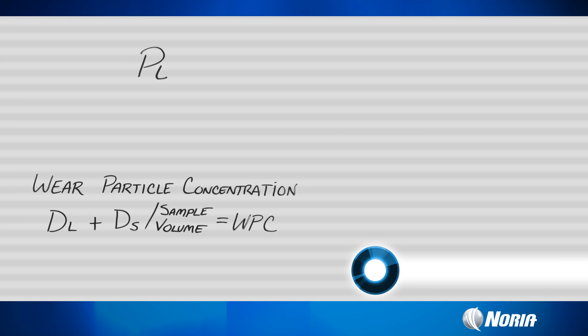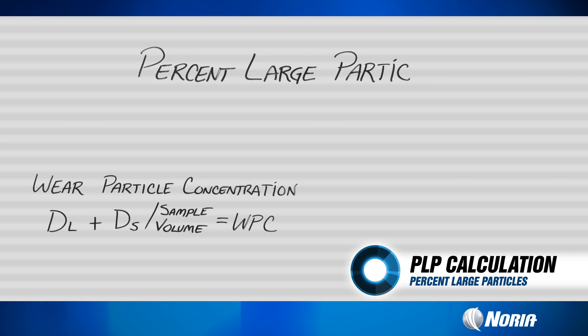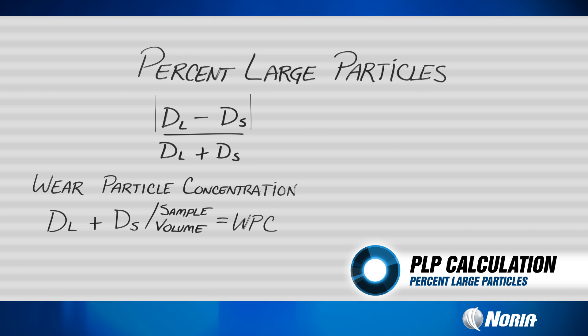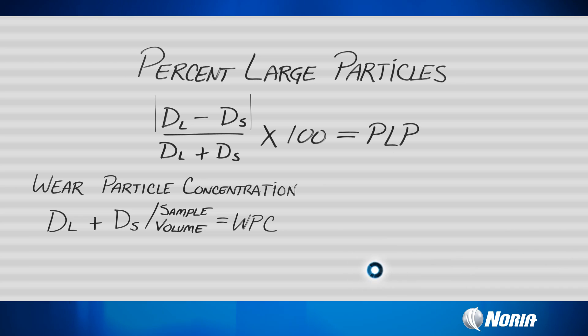The second piece of information we can calculate is called the percent large particles, or PLP. This calculation takes the absolute value of ferrous large minus ferrous small, divided by ferrous large plus ferrous small, then multiplied by 100 to get the percent large particles.